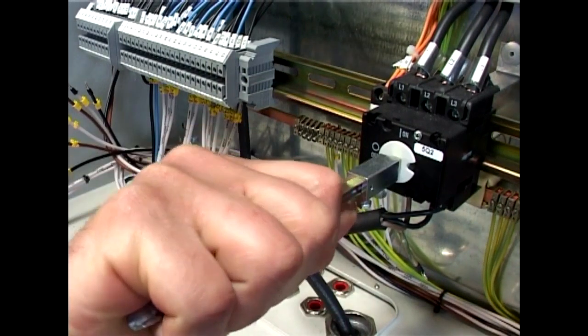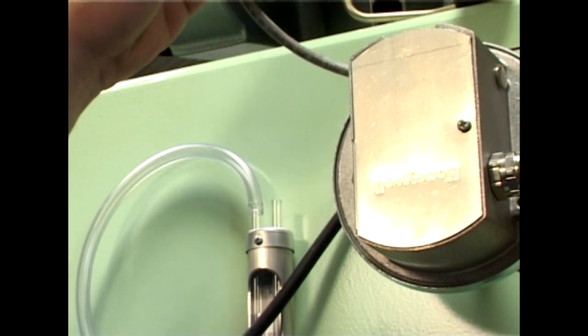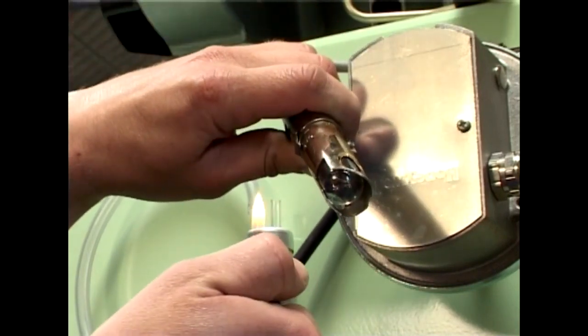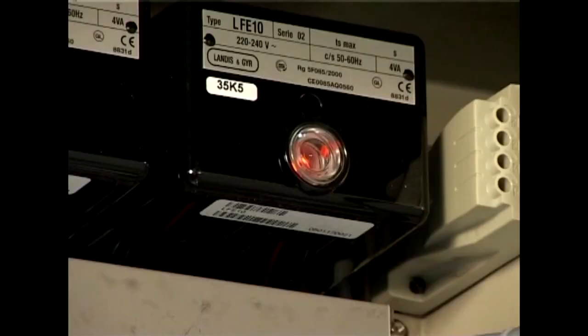If you want to check the functionality of the flame detectors, this can be done by placing a lighter in front of the flame detector and monitor that the bulb on the flame control boxes lights up.